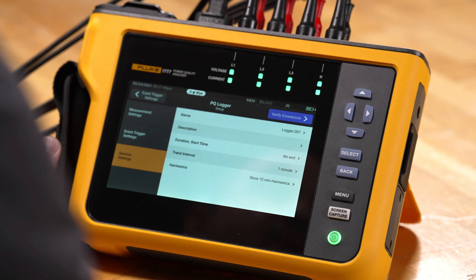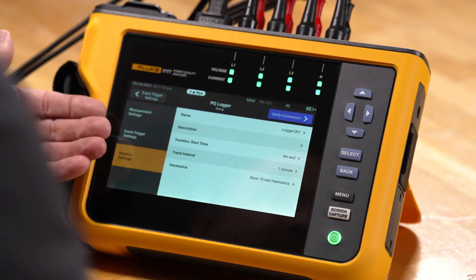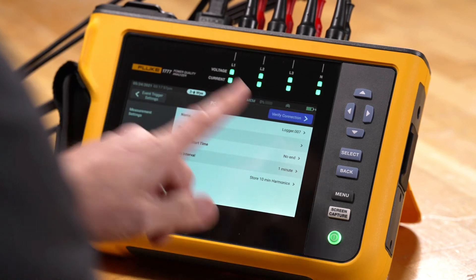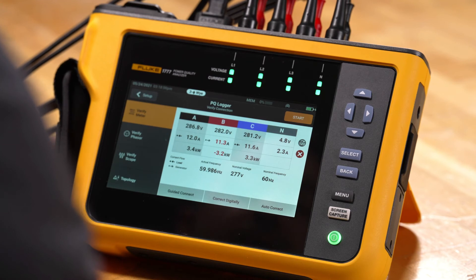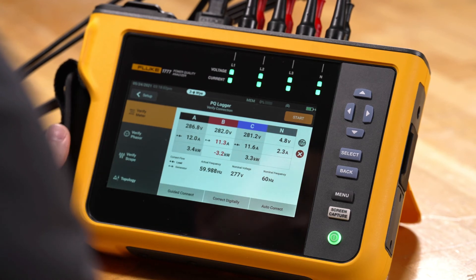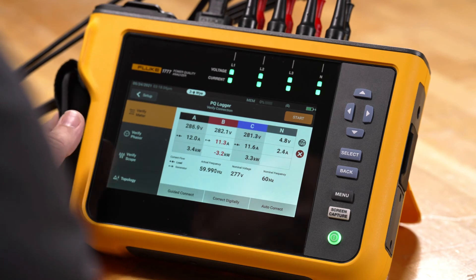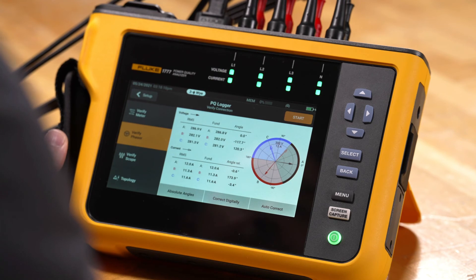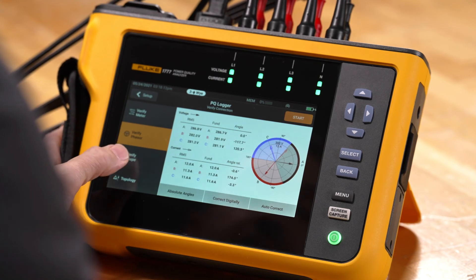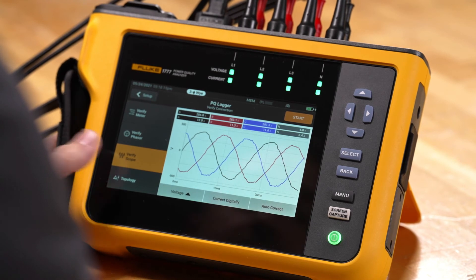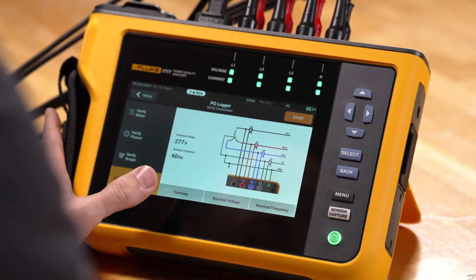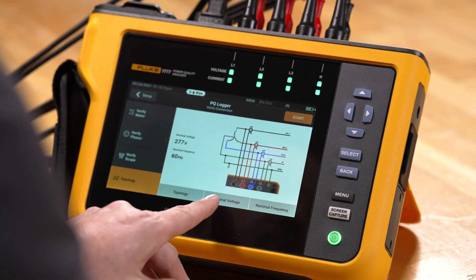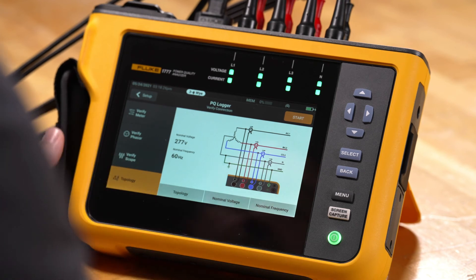The next step is to verify configuration. Once we've verified our settings are correct, we go to verify connection on the screen and tap verify connection. That puts us into a screen showing our live active voltages, our power, and our current numbers. If we click verify phasor we get our vector diagram, and we can also go to verify scope to look at waveform data. We can also go to the topology to change from wye to delta or a various power configuration, and change the nominal voltage as well as the nominal frequency.